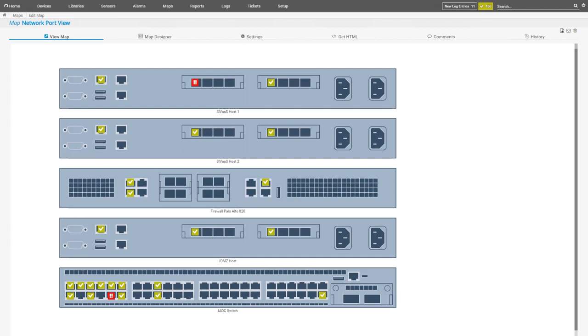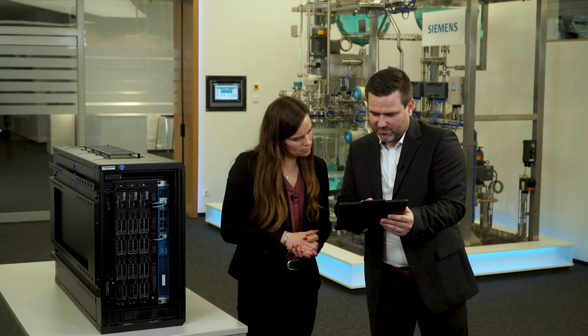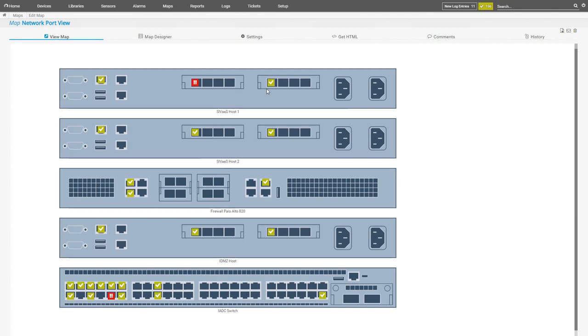Now you can already see a management interface on server 1 is shown as defective. We can also see the matching counterpart displayed as down on the switch. The system administrator can now easily check this connection and isolate the error very well. Of course, our IADC has redundant management networks, so the interruption of a single network connection is not a problem. That's the main advantage of the monitoring system — it displays a fault in the system which does not yet have any effect on production. The system administrator already knows that something has to be done before production even notices. Now the problem can be fixed without any damage. This significantly increases the availability of the overall system and reduces the risk of system failures.